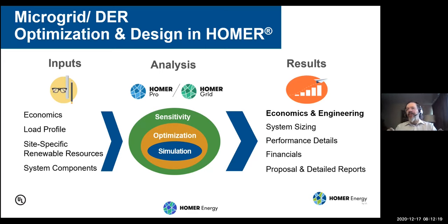How is that system gonna operate? If it has a backup generator, how much fuel is it gonna use? How much are the batteries gonna get used? Is the load gonna be fully met, et cetera? And that tells you what it's going to cost to build and operate that system. That's one system. Then it will do that same simulation for hundreds of potential systems and rank them by cost of energy or net present cost to find the least cost system.